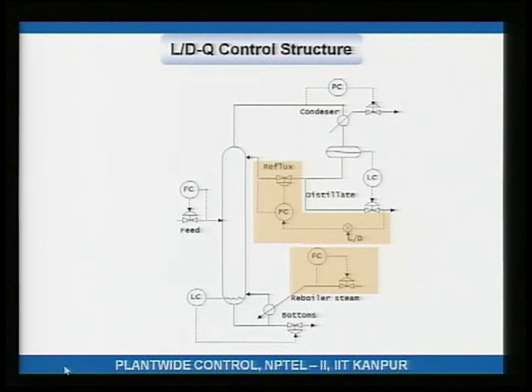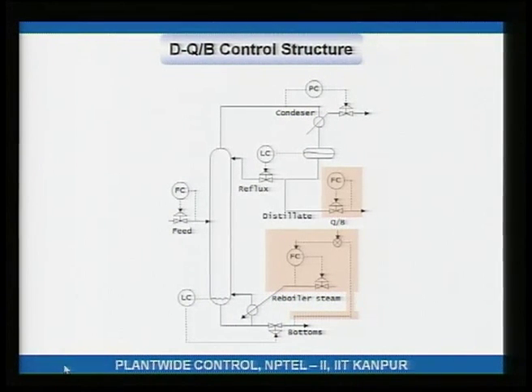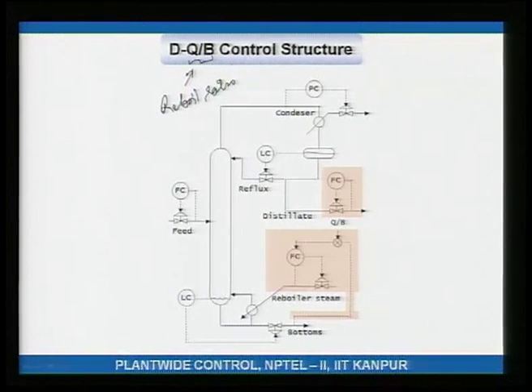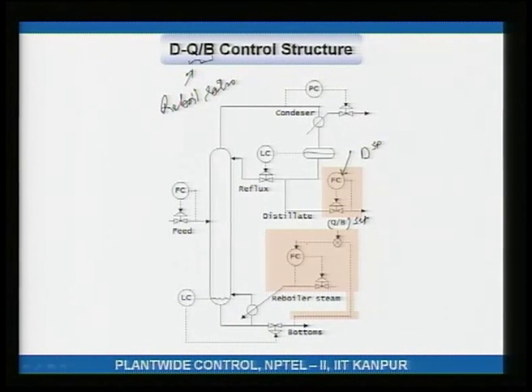Similarly, there is an L/D, Q structure where the operator sets Q and L/D. There is also a D, Q/B structure where Q/B is called the reboil ratio. The bottoms flow is measured and multiplied by the Q/B set point to give the steam flow set point, and the steam flow controller moves the valve accordingly. The operator sets D and the reboil ratio.